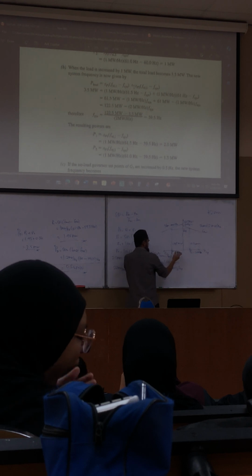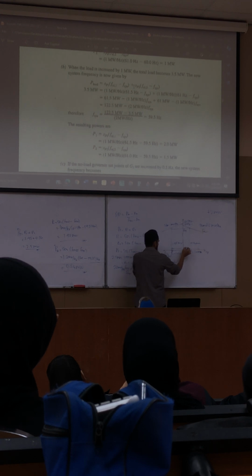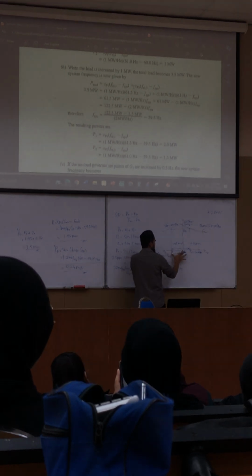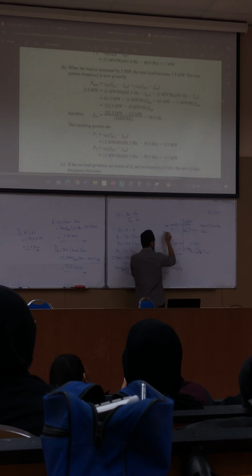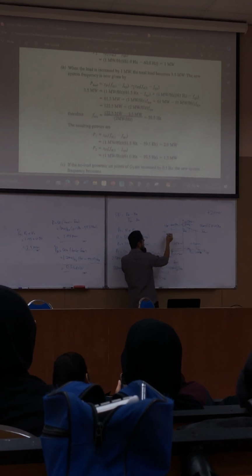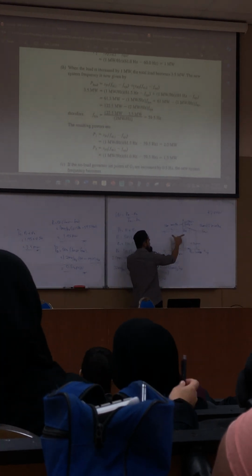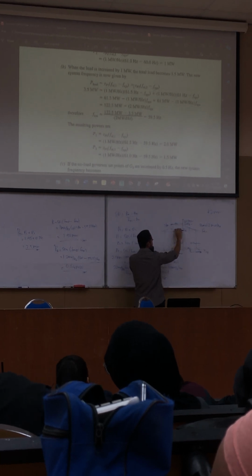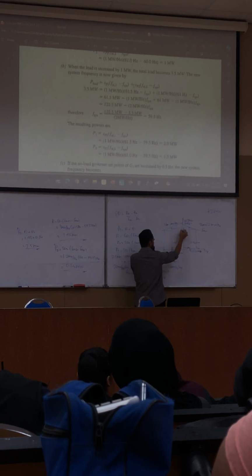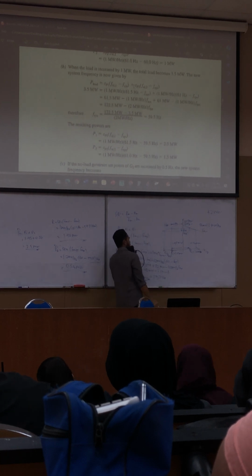If we add, that means the portion will increase. The width of your power will increase. When it increases, it is limited by this roof, so it has to go down further. Understand? It is limited by the roof. So when you want to widen your power, you have to reduce your system frequency because of the limit by this roof. So the system frequency will fall to the next F system, F system prime.